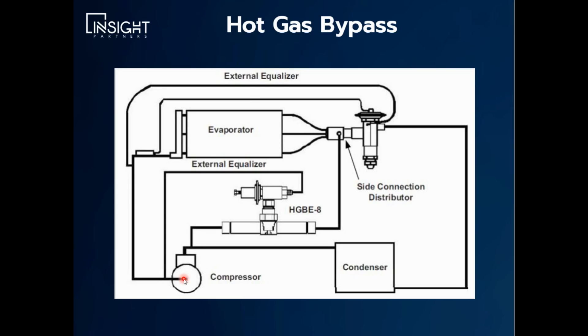The choices are to shut off your compressor or to try and keep it on longer, which is generally what we want to do — keep the compressor running to dehumidify and cool the air. So what hot gas bypass does is it takes some of the gas from the compressor, runs it through this bypass valve, and sends it into the inlet of the evaporator coil. You're falsely loading the evaporator coil with some heat load, just like you were adding load to the air coming across the evaporator coil. This valve is a purely mechanical device — usually there's a bulb strapped to this line here that measures the temperature, and that changes the pressure in this line, which allows a spring to open and close. So it doesn't really have any controls — it's just totally mechanical. Hot gas bypass is purely a freeze prevention mechanical device. It has nothing to do with reheating the air.